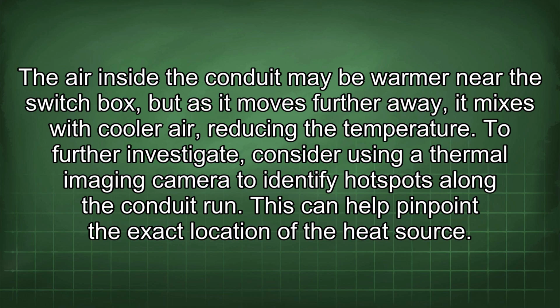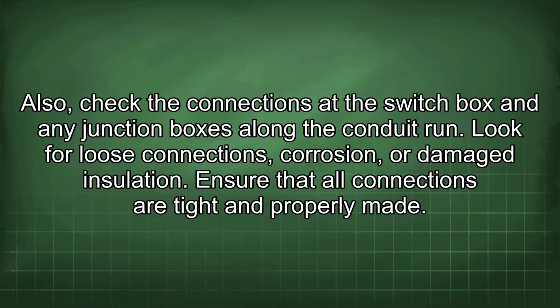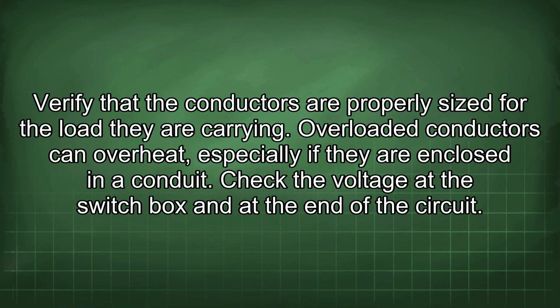To further investigate, consider using a thermal imaging camera to identify hotspots along the conduit run. This can help pinpoint the exact location of the heat source. Also, check the connections at the switch box and any junction boxes along the conduit run. Look for loose connections, corrosion, or damaged insulation. Ensure that all connections are tight and properly made. Verify that the conductors are properly sized for the load they are carrying. Overloaded conductors can overheat, especially if they are enclosed in a conduit.